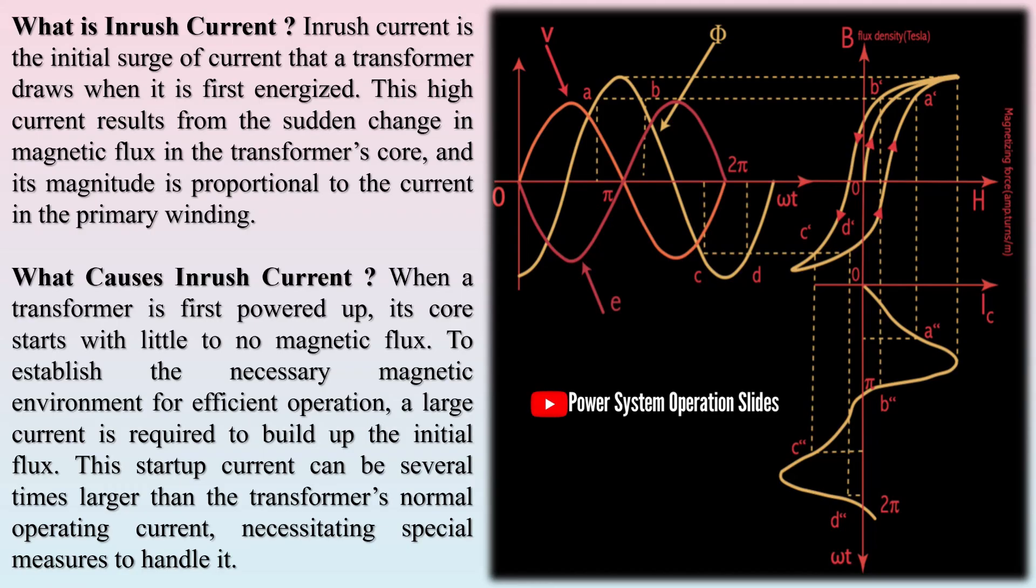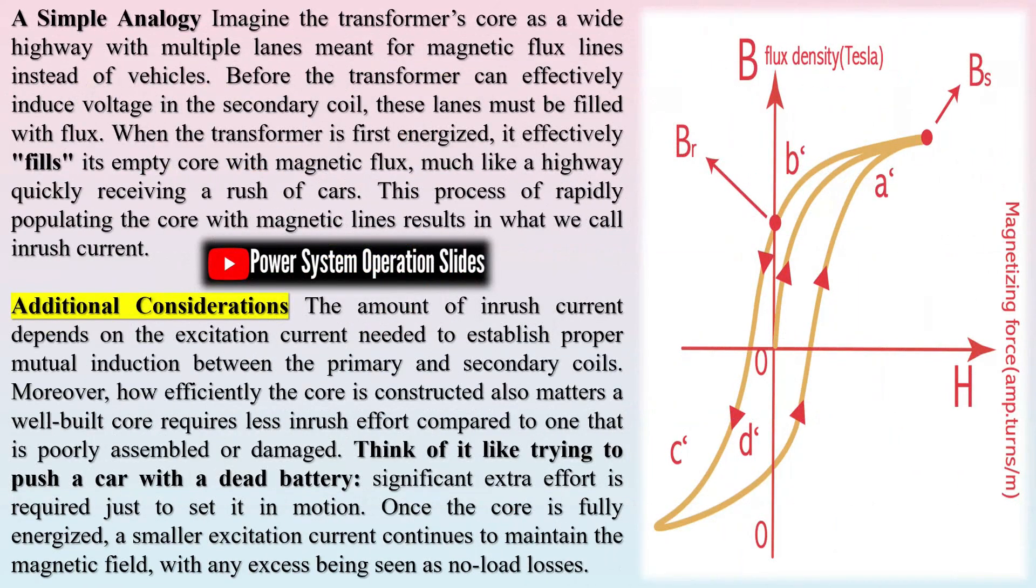When a transformer is first powered up, its core starts with little to no magnetic flux. To establish the necessary magnetic environment for efficient operation, a large current is required to build up the initial flux. This startup current can be several times larger than the transformer's normal operating current, necessitating special measures to handle it.